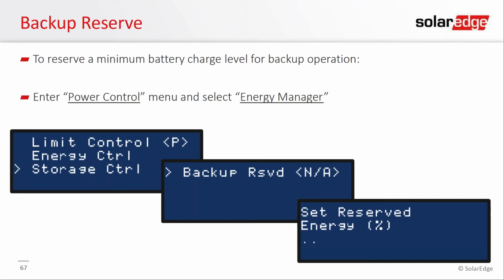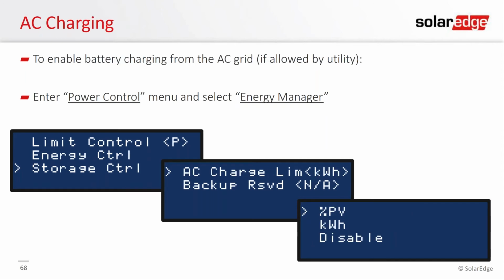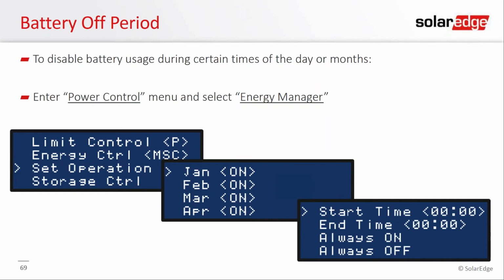Storage control, you can also set up your backup reserve. What this does is it tells us I want to reserve a certain amount of space in my tank, in my battery pack, for backup. So if I'm going to do time of use arbitrage, maybe I only use time of use for 70% of the battery, and then the other 30% is always reserved for backup. We can enable AC charging, and you can say, I want an AC charge limit as a percentage of the photovoltaics that's installed, or maybe some kilowatt hours, or you can disable it. So those are a couple of the menu options.